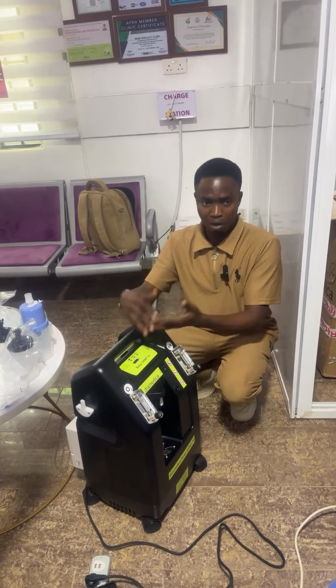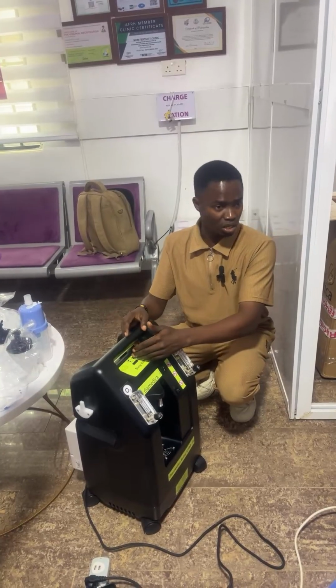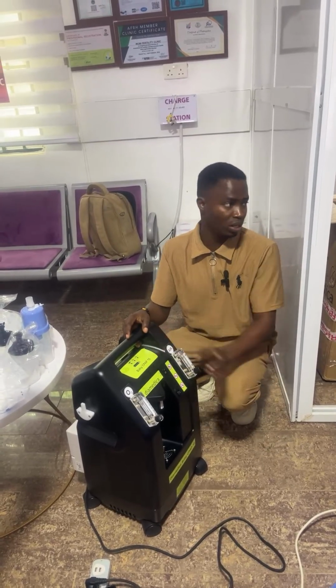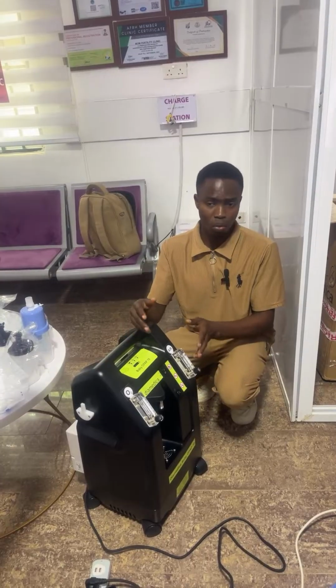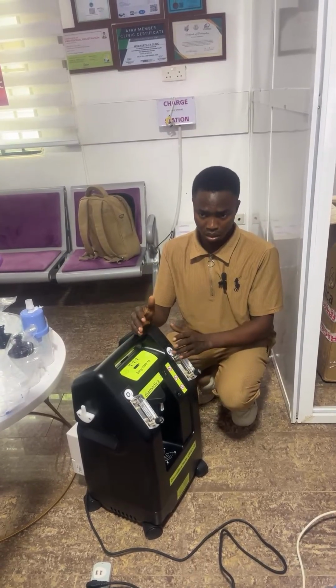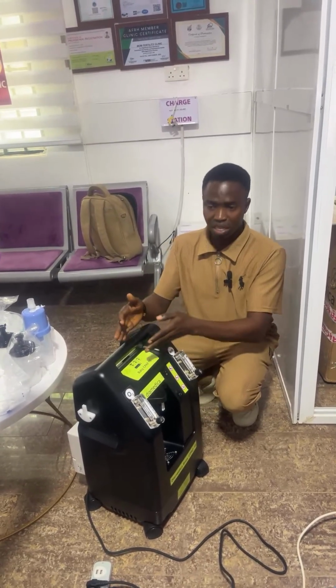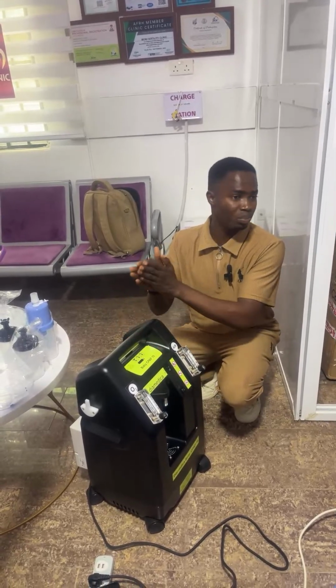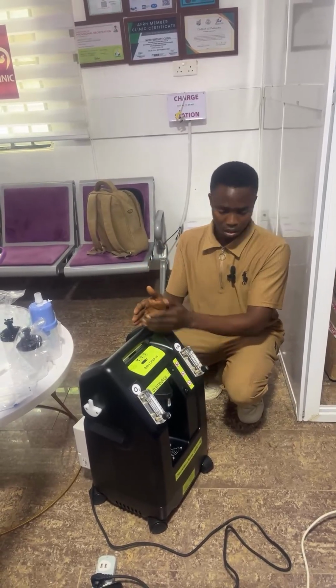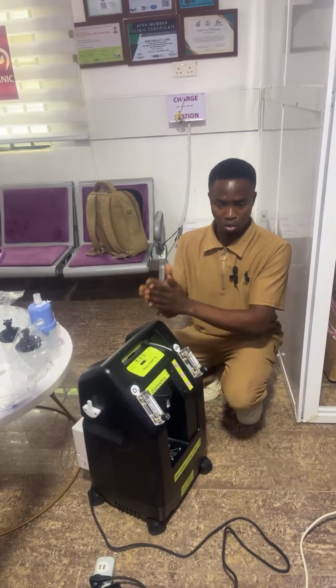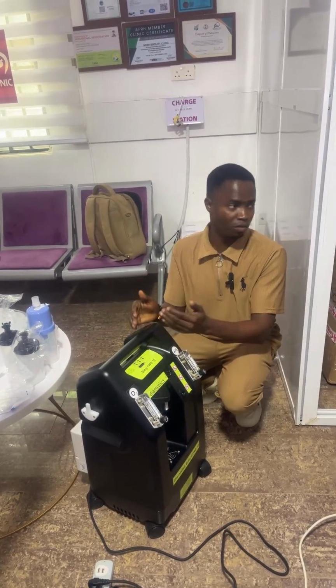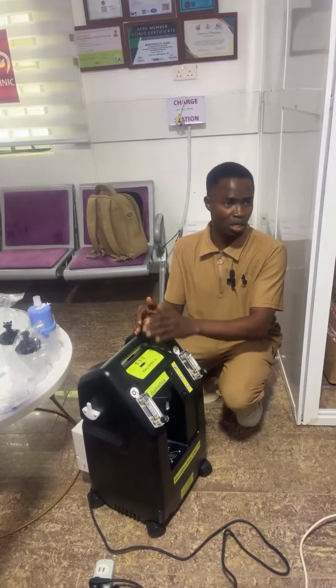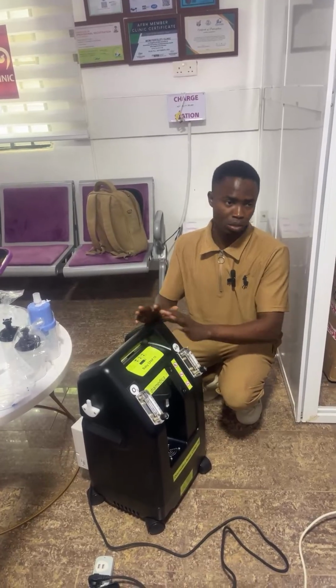Even if you have an emergency and the light is yellow, you can still use it. But if it's red, you can't use it. You have to check what's the cause. You understand? Even if it's still yellow, it means there is oxygen, but it's not 100% yet. But if it's green, it means it's 100%. Meanwhile, in case of emergency, you can still use it on yellow. It's not bad. But if it's red, don't use it.